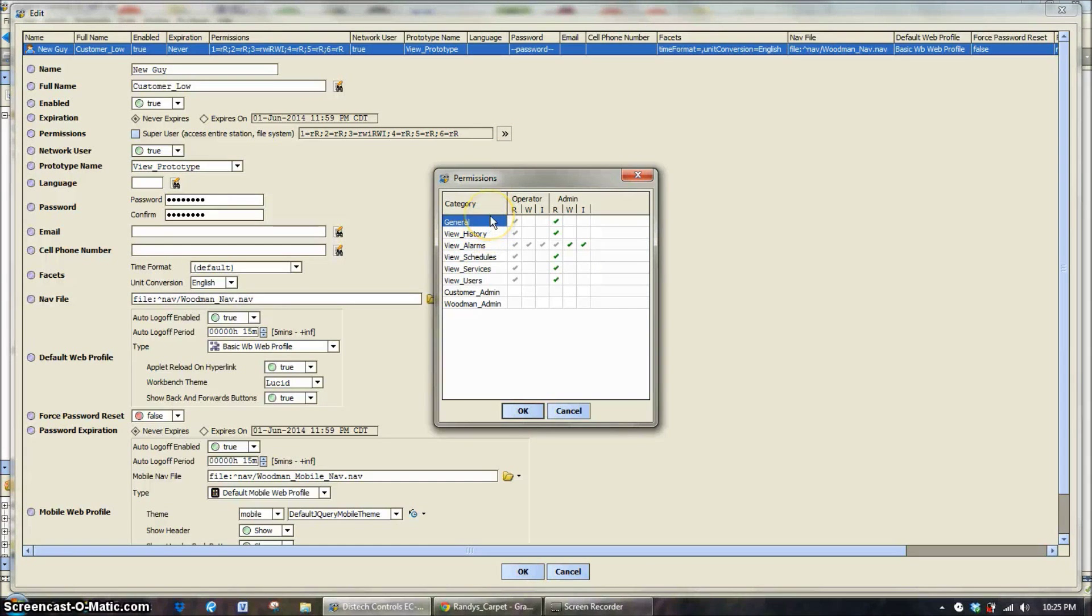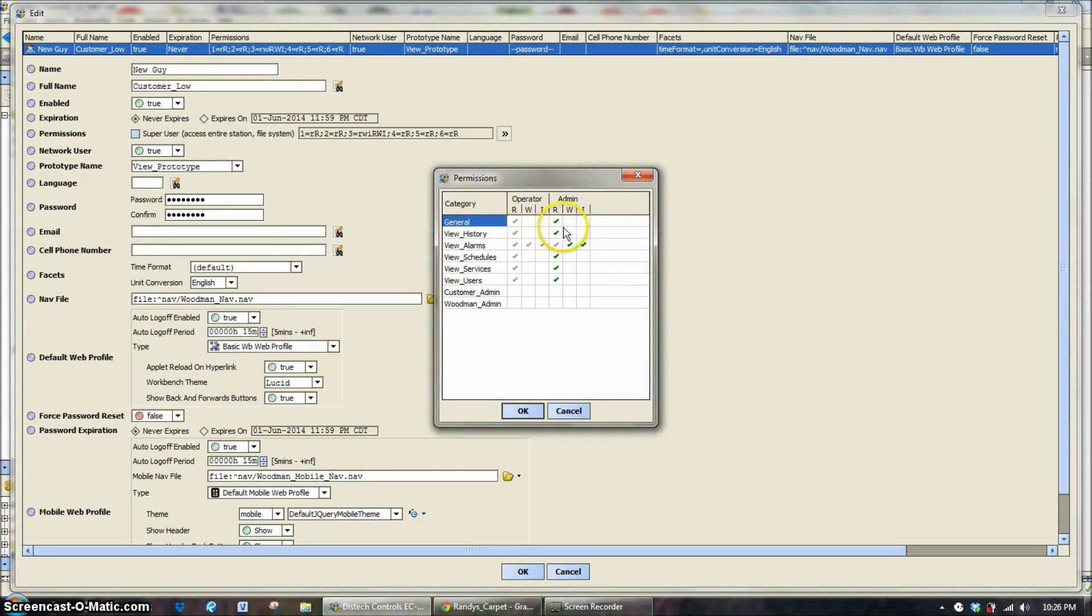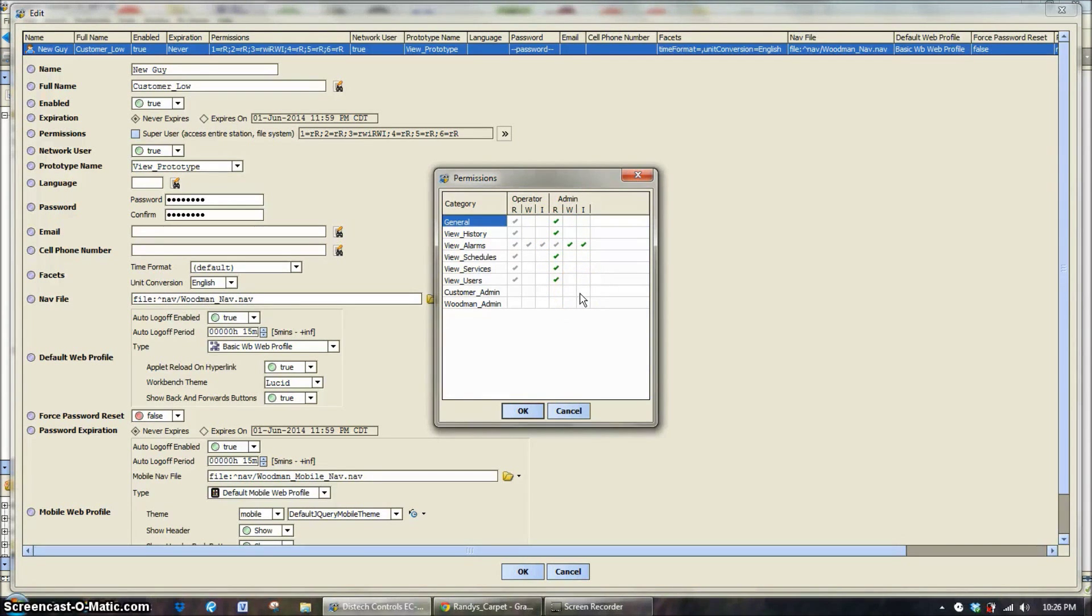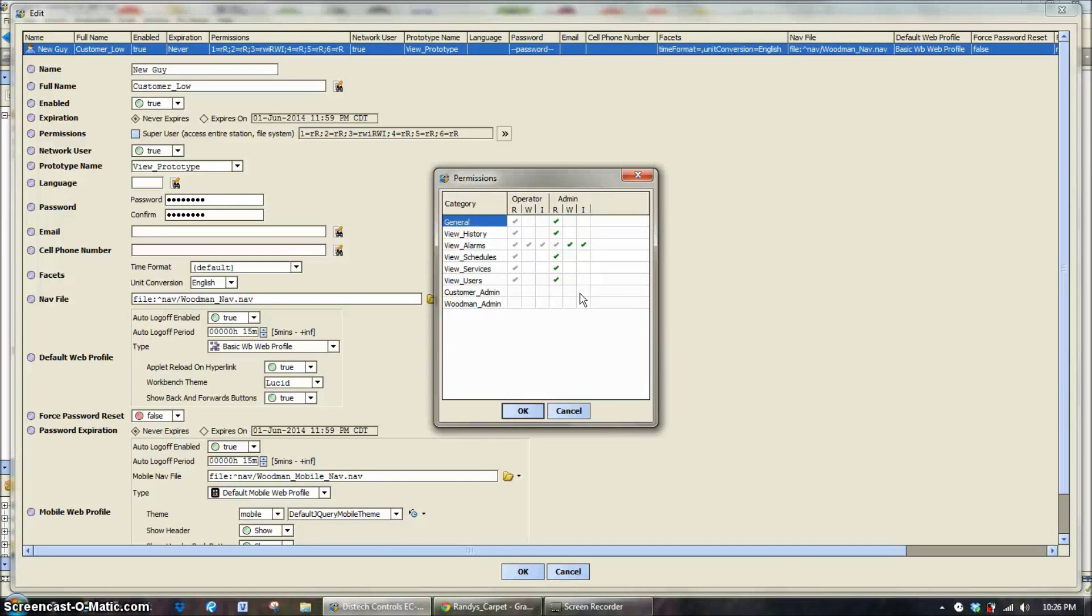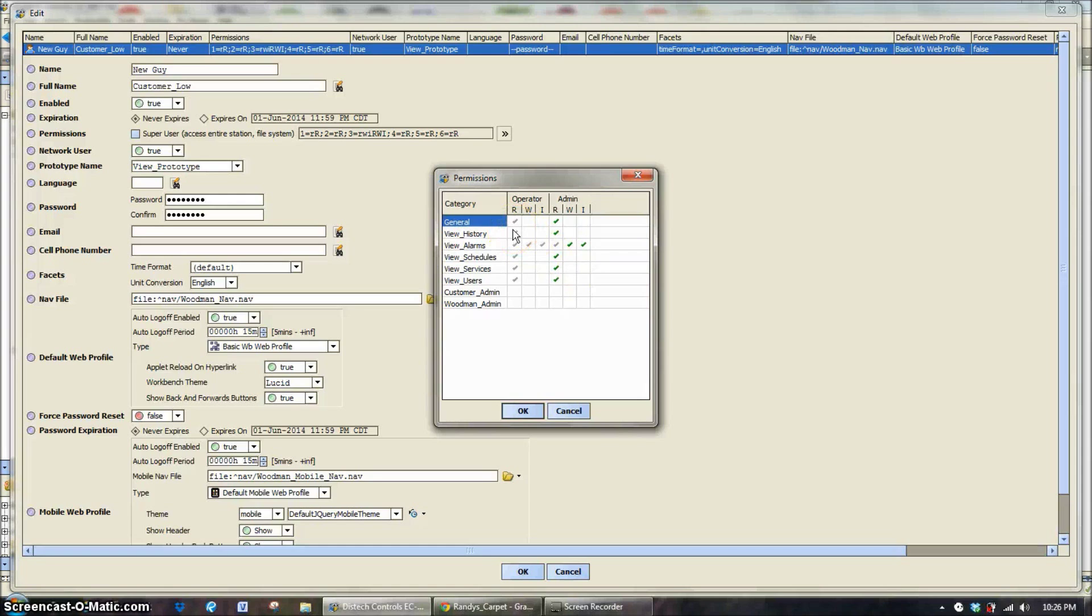General is going to be just looking at graphics. In this case, since it's a low customer level, they're able to read and they're going to be able to read and see operator level and admin level type things. When they look at a piece of equipment, they're going to be able to see the set points, see the space temperatures, see all that stuff, but they're not going to be able to change any of it. Same if they go to look at histories for space temperature.